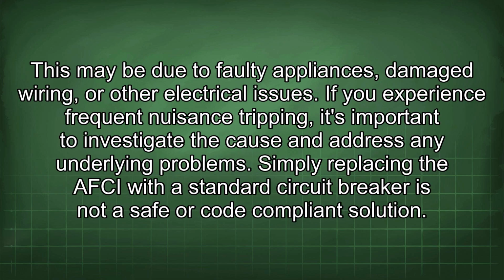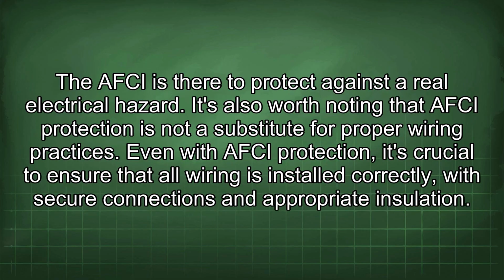This may be due to faulty appliances, damaged wiring, or other electrical issues. If you experience frequent nuisance tripping, it's important to investigate the cause and address any underlying problems. Simply replacing the AFCI with a standard circuit breaker is not a safe or code-compliant solution. The AFCI is there to protect against a real electrical hazard.